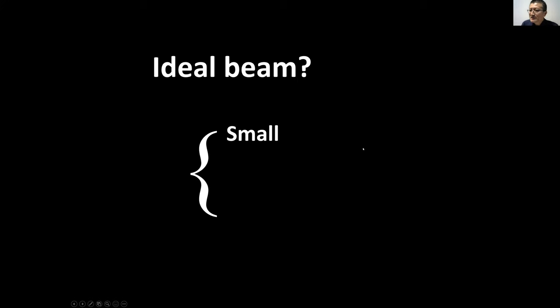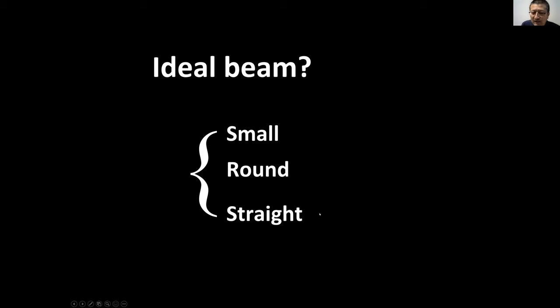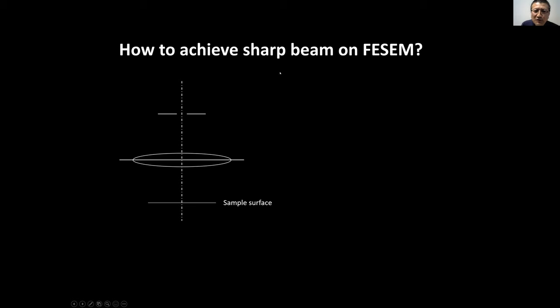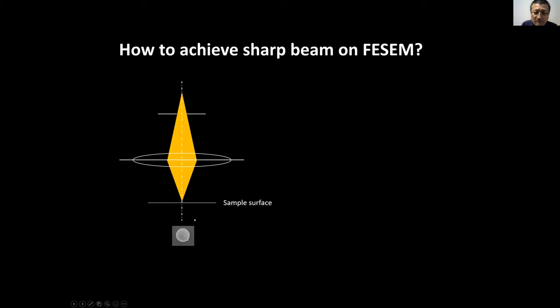So an ideal beam needs to be: small (for better resolution), round in shape, and straight (well-aligned). How do you achieve a sharp beam? As a user, one thing we can do is focus the beam. When we focus the beam correctly onto the sample surface, we get a sharp image. If the focus is below the surface (under-focus) or above (over-focus), the cross-section of the beam is bigger and the image won't be clear.